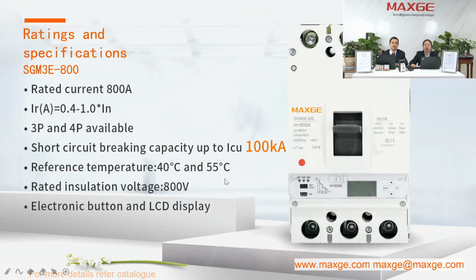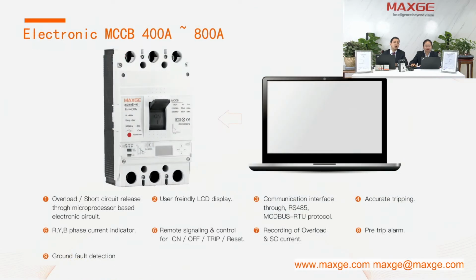This is a specification of our 800 ampere electronic type. Now I will tell you more detail about the features of the electronic MCCB. The main feature of the electronic MCCB is that it can be programmed. So how can it be programmed? It has an add-on module which can be connected to our laptop or a computer, and there we can do the programming for the long delay current, then the long delay tripping time, then the short delay current, short delay tripping time, and also the pre-trip alarm. And in the 4-pole we have the ground fault detection current also. This can also be programmed.